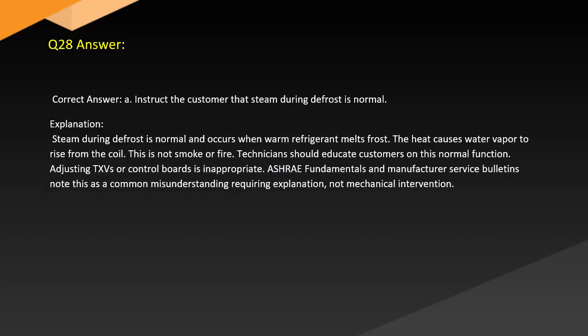Answer. Correct answer: A. Instruct the customer that steam during defrost is normal. Explanation. Steam during defrost is normal and occurs when warm refrigerant melts frost. The heat causes water vapor to rise from the coil. This is not smoke or fire. Technicians should educate customers on this normal function. Adjusting the TXV or control boards is inappropriate. ASHRAE Fundamentals and manufacturer service bulletins note this as a common misunderstanding requiring explanation, not mechanical intervention.